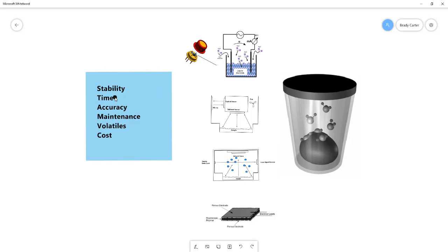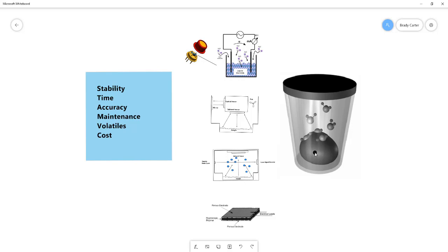In terms of time, analysis time, the thing that has to happen for a measurement to be taken, there are several steps. One is you have to reach vapor equilibrium. And for each sample type, there is a different amount of time that that requires. High fat samples take longer, some samples can take less than five minutes. Once that vapor equilibrium is achieved, then you can take a measurement on the relative humidity and get the water activity, the equilibrium relative humidity. The requirements that are set to indicate that equilibrium has occurred can also vary. And so this means the only way to track equilibrium is to know that you're in a static state. So there aren't any changes over time. And so what's used is a setting that looks at water activity values over time. And when the variation drops to a certain preset level, that indicates the end of the test. And so the more stringent you set that, the more likely you are to have equilibrium, but it also extends the test time. And so if there are differences between those settings, it will result in differences in analysis times.